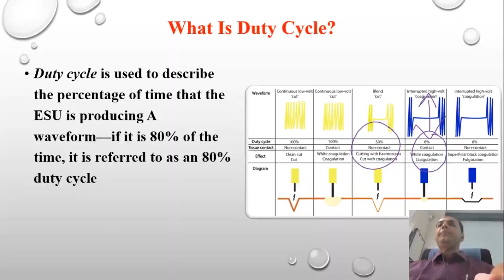Cutting is best achieved by a waveform consisting of 100% duty cycle, a non-modulated continuous waveform which has a peak voltage of more than 200. Blended waveform is produced by duty cycles ranging from 30 to 80%. Coagulation waveform is modulated, high voltage but dampened, meaning the peak voltage decreases like this. It is not that a single waveform functions as a cutting waveform or coagulating waveform.